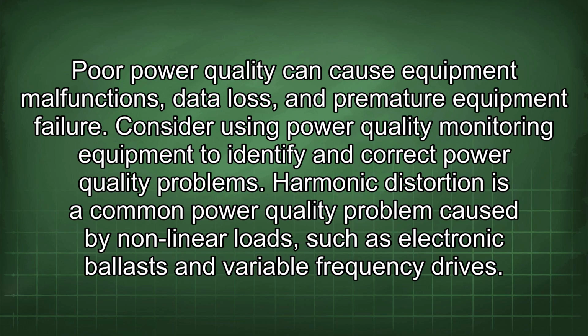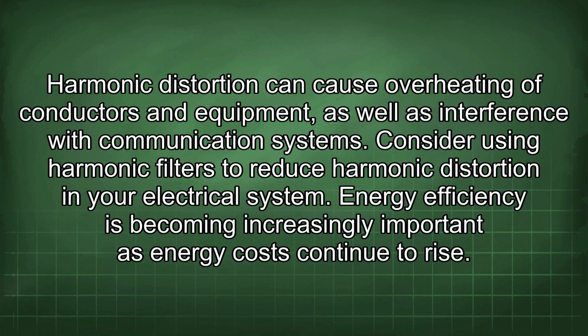Harmonic distortion is a common power quality problem caused by nonlinear loads such as electronic ballasts and variable frequency drives. Harmonic distortion can cause overheating of conductors and equipment, as well as interference with communication systems. Consider using harmonic filters to reduce harmonic distortion in your electrical system.